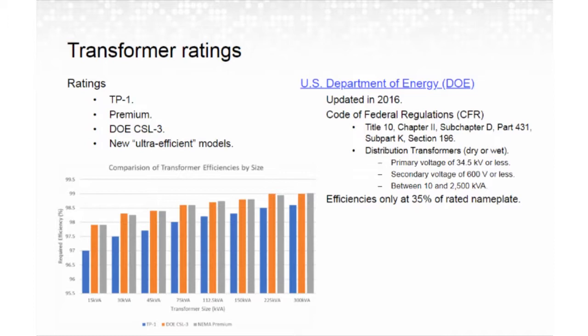So the left group is the 15 kVA rating, and the bars represent TP1 in blue, CSL3 in orange, and NEMA Premium in gray. The transformer size increases from left to right up to 300 kVA to identify that as a transformer increases in size, the required efficiencies also increase. The graphic also identifies the increase in efficiency requirements between the three classifications. Now, it's important to note that these efficiency ratings are at a 35% transformer load and using only linear or resistive loads. When sizing transformers, though, we need to take loading into consideration, and it's important for the reasons that we're going to discuss next.